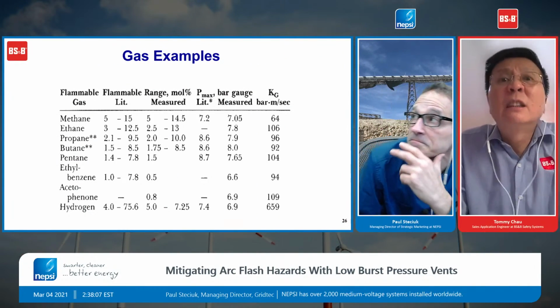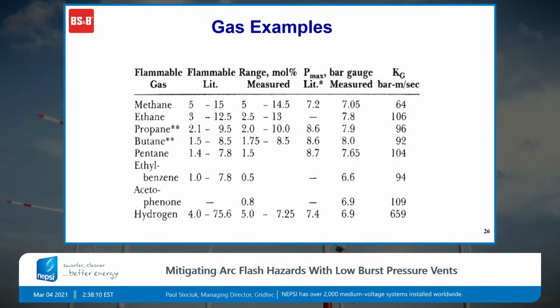KG value for different types of gas. For protection, propane is normally what we would use for reference, but as you can see, some common types of gas are on there for gas explosion. When we do the calculation, we will need the KG value.